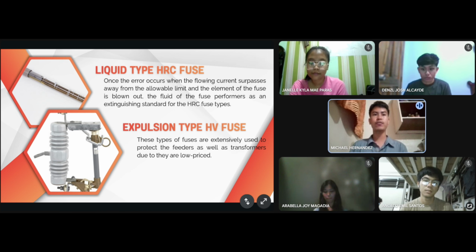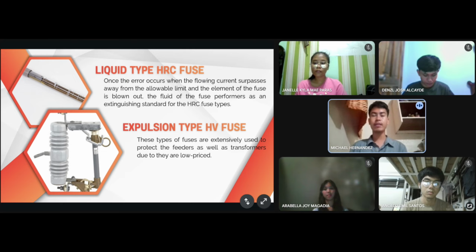The expulsion HV fuse acts like a safety valve for high voltage systems. When too much electricity tries to flow through, the fuse sacrifices itself to protect the rest of the system by safely cutting off the power. These fuses are often found on overhead distribution lines and transformers in power networks because they are reliable, relatively inexpensive, and easy to replace. However, since they release hot gases and make noise when they operate, they're typically used outdoors or in well-ventilated areas.